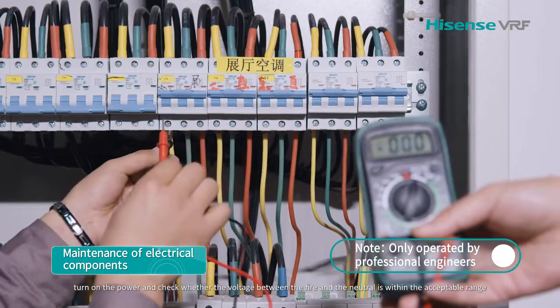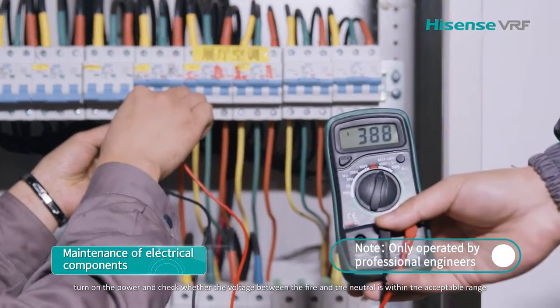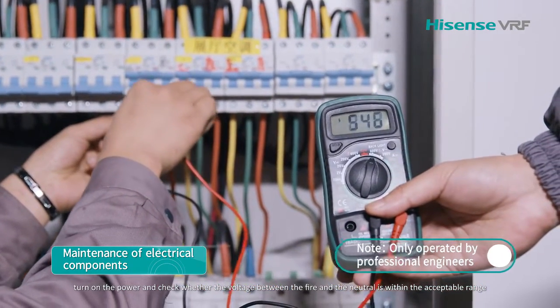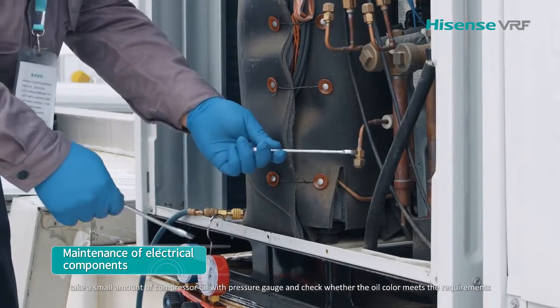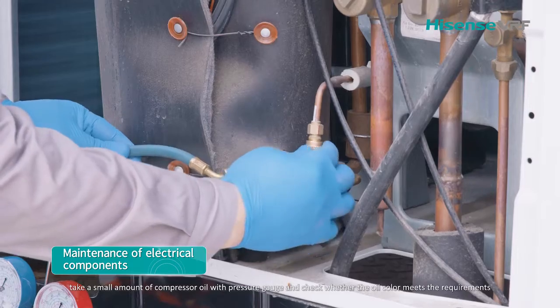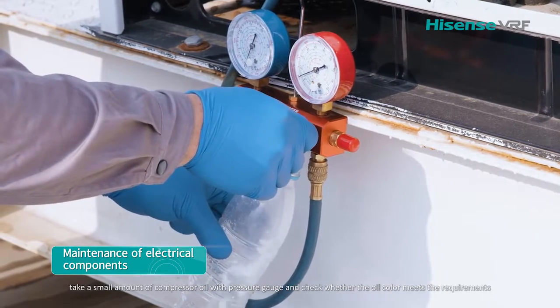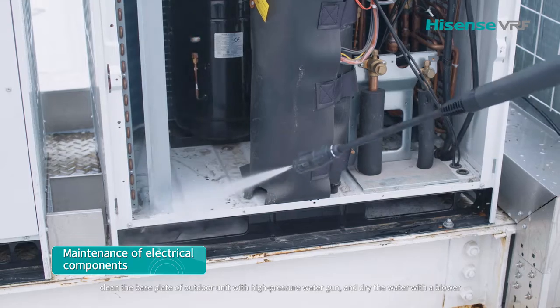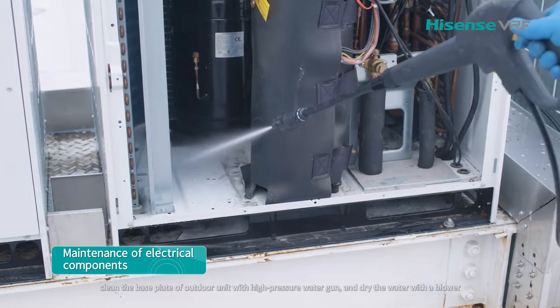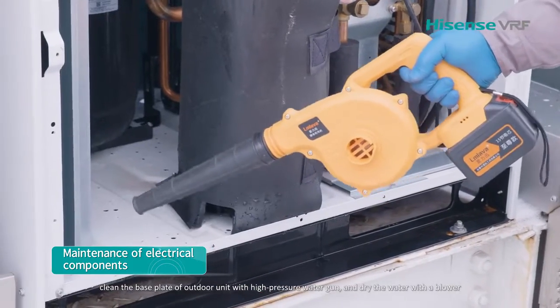Turn on the power and check whether the voltage between the live and the neutral is within the acceptable range. Take a small amount of compressor oil with a pressure gauge and check whether the oil color meets requirements. Clean the base plate of outdoor unit with a high-pressure water gun and dry the water with a blower.